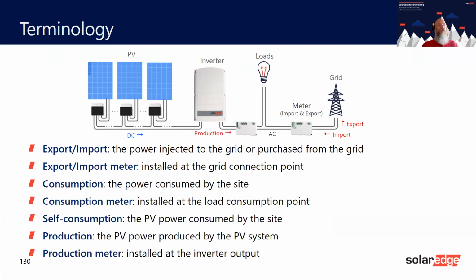If you're using it for consumption or production, production would be in line of the circuit, and that would be before any other loads or any other circuits are taken from it. And if you wanted consumption, you would put the meter here to measure the load. And again, for consumption, the CT would have to face this way towards the load.